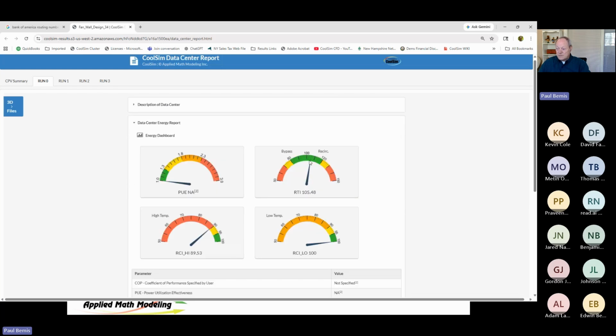We're above 100%. Our RTI is 105. So even in the steady state case, I have set this one up and I just ran this. I don't really even know when I ran this, but I can tell right away we're having trouble. And look, my RCI is showing 90. I'm getting into the red. I've got problems here because my airflow is insufficient.